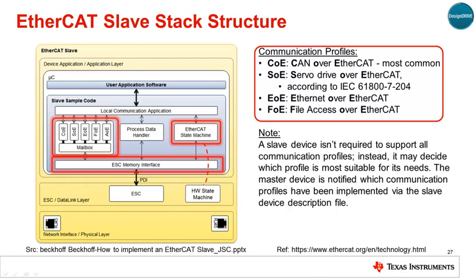Additional profiles include SOE, or servo drive over EtherCAT; EOE, or Ethernet over EtherCAT, which enables EtherCAT to transport standard Ethernet packets in the EtherCAT datagram; and FOE, or file access over EtherCAT, which finds use in bulk transport such as firmware updates. Note that any given slave isn't required to support all profiles — only those needed in a particular slave's application need be included. The slave device description file provided to the EtherCAT master specifies which profiles are available.